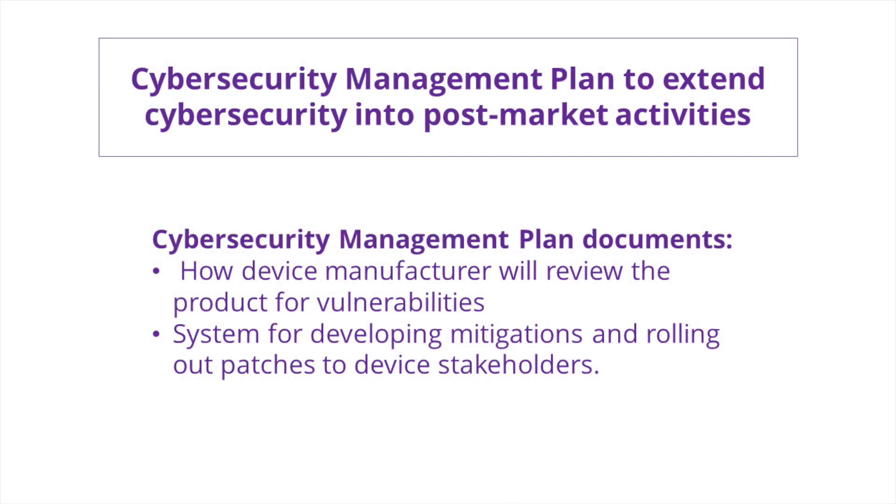The FDA wants to ensure that cybersecurity is extended into post-market activities through the Cybersecurity Management Plan. The plan documents how the device manufacturer will review the product for vulnerabilities and have a system in place for developing mitigations and rolling out patches to device stakeholders.